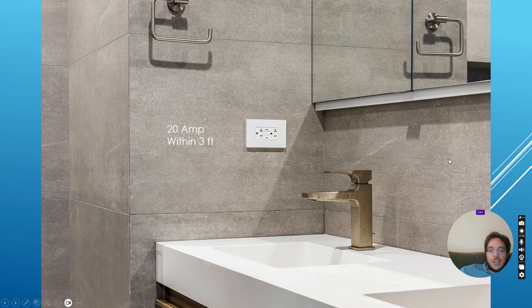If you've got 2 sinks, they can share a receptacle in the center, or you could put separate ones, doesn't matter. But it's got to be within 3 feet or 1 meter in Canada of the sink, and it has to be at least 3 feet or 1 meter away from the shower, where practical. So sometimes it's not possible, and if it's not possible, then it's not possible. And it's got to be GFCI rated.